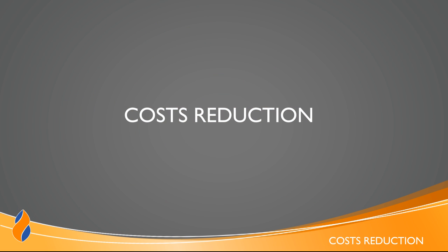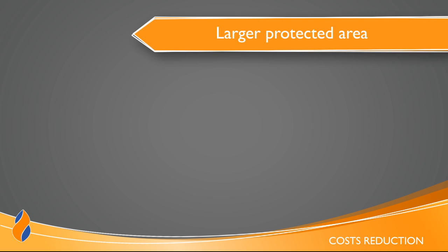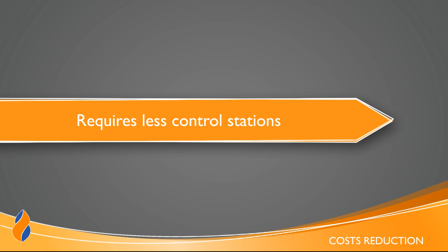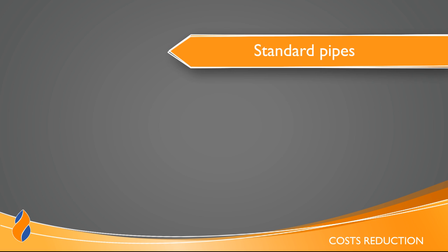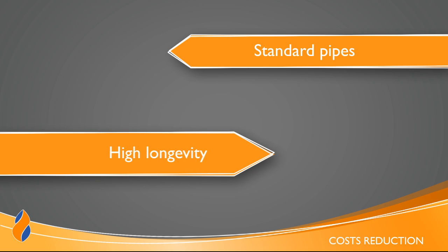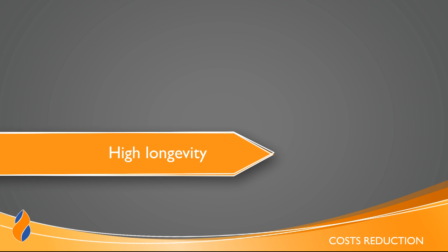The VACTEC vacuum sprinkler system is cheaper than classical systems, both on operation and maintenance costs. The protected area is larger. Indeed, the vacuum system, compared to a dry system with similar capacity, requires less control stations. It can be installed with standard pipes, whereas the dry system requires pipes with higher quality. The VACTEC system longevity is higher because it avoids clogging and corrosion as seen previously.